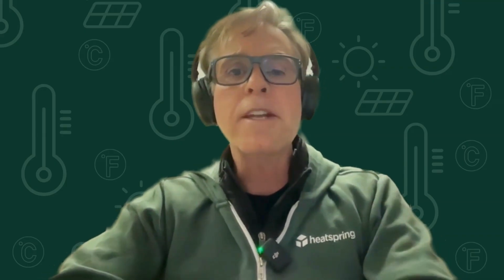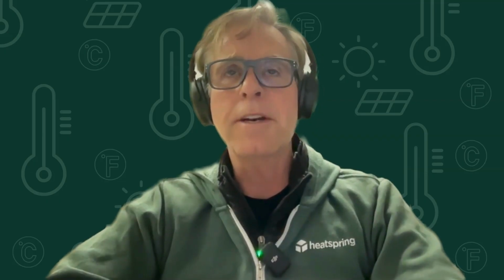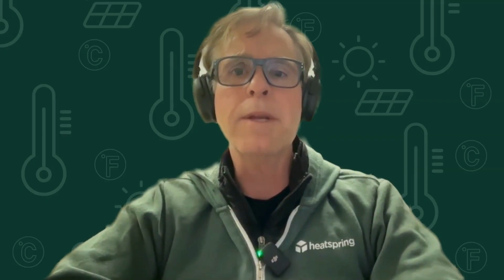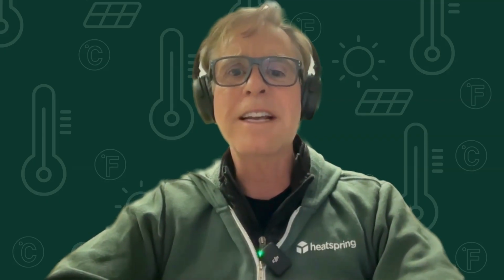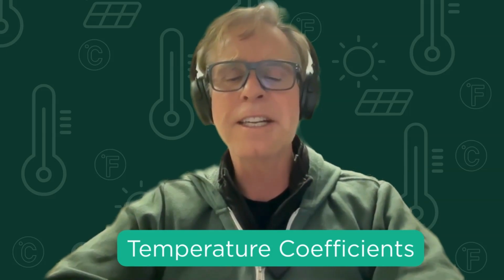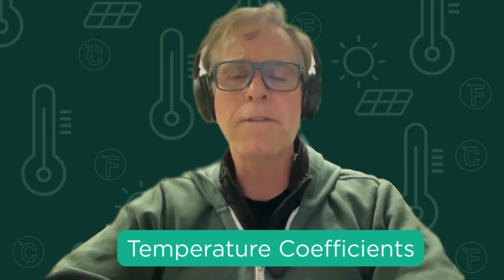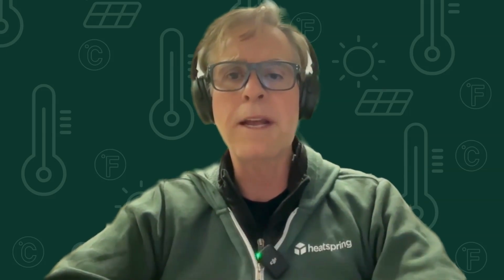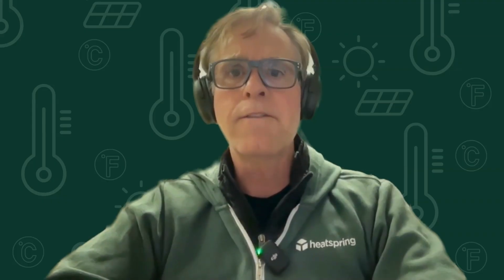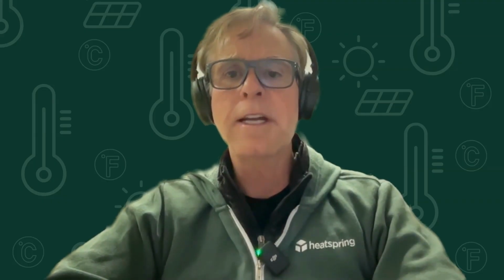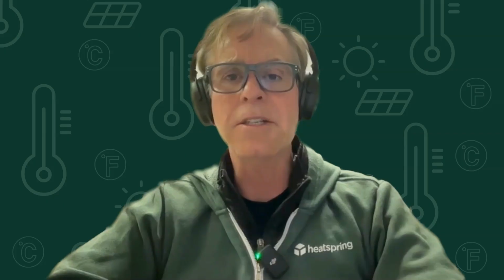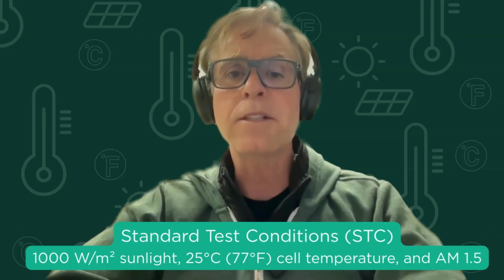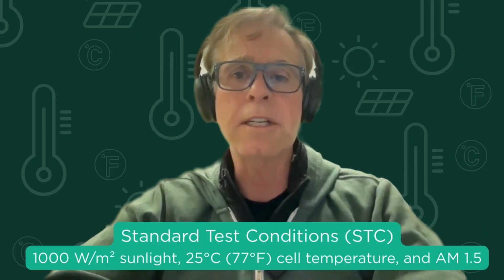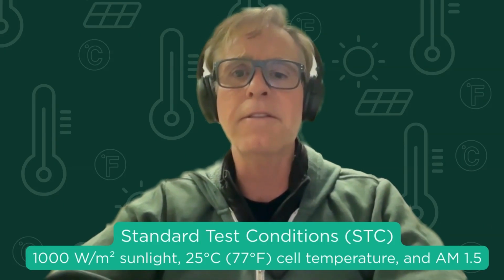So anyway, what you do for these calculations, there's a couple of different ways of doing it, but the main way that people deal with it is there are these things called coefficients, such as the temperature coefficient for voltage that you'll get from the solar manufacturer. And you figure out what difference in temperature there is from the conditions the solar module was tested at, which is usually 25 degrees Celsius, 77 Fahrenheit.